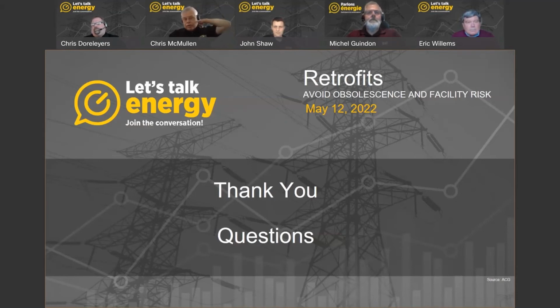I'll add too that with new units we've come with Ethernet communications, Modbus, remote monitoring, remote dialers. It's incredible the optics a customer can have on their generator from a monitoring standpoint. Lots of times the power goes out and we didn't realize the breaker was tripped, or the unit wasn't put back in auto, just because older systems couldn't provide that remote communication for monitoring purposes.